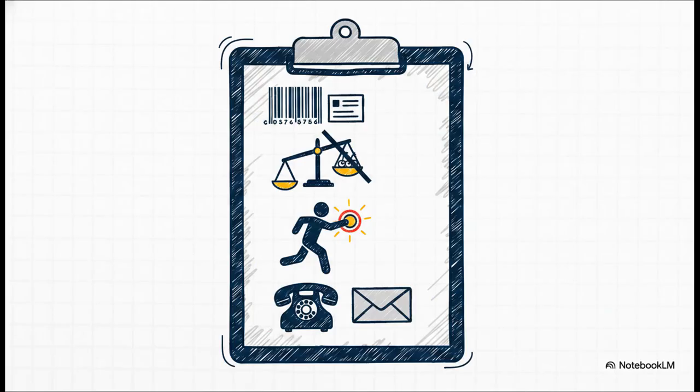When you're drafting that FSN, you have to use the standard European Commission template. No improvising. It needs to include unambiguous identification details, like the UDIDI and your single registration number. The clinical description of the malfunction must be totally balanced, meaning no cherry-picking the positive data just to obscure the true risk profile. Finally, don't leave your users guessing. Give them precise, actionable instructions on exactly what they need to do with the device next, and make sure your contact information is crystal clear.